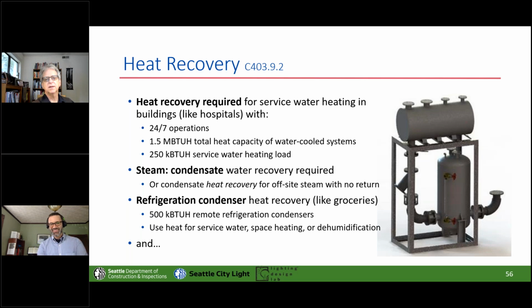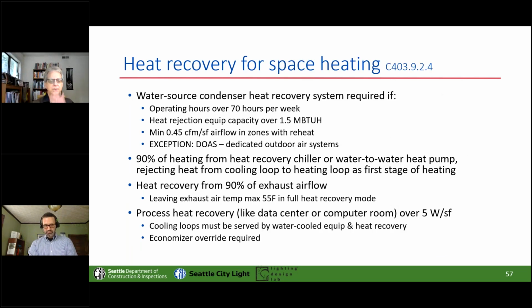Okay, so heat recovery for space heating is required if you have operating hours that are, say, longer than a traditional office building or school, and you've got large cooling towers and so forth. If you've got a DOAS, then that requirement goes away. You've got to take heat recovery from at least 90% of your exhaust airflow, and if you've got process heat, then you've also got to grab that additional heat. This is like heat that's already been created once and can be used again as low-grade heat for space heating.